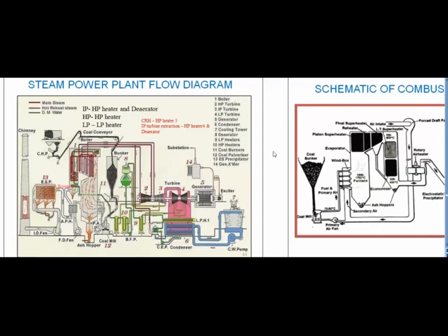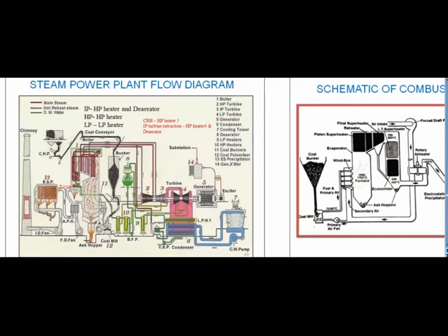In the furnace, coal powder burns more like a gas than a solid fuel. The air required for proper combustion is called secondary air, and it is supplied through wind box dampers located at all the 4 corners of the furnace.